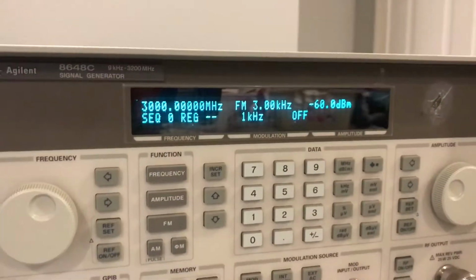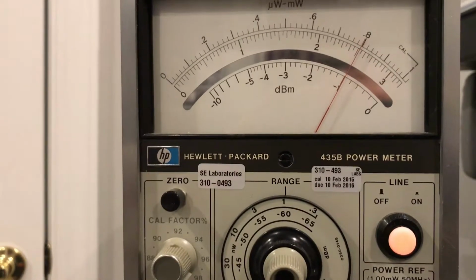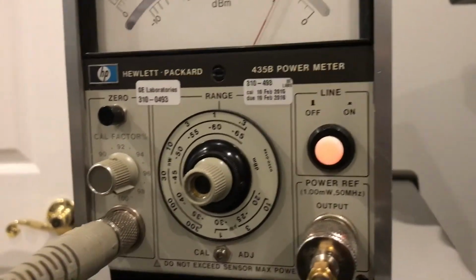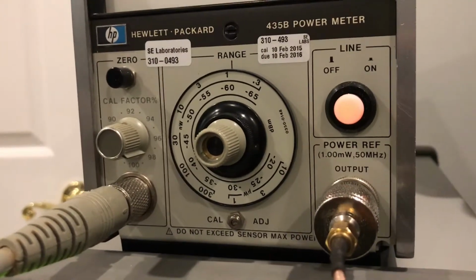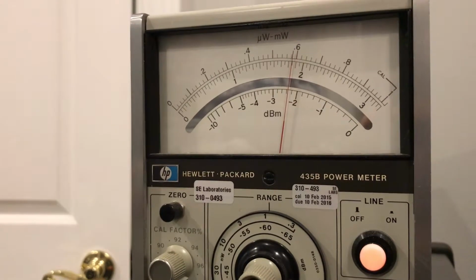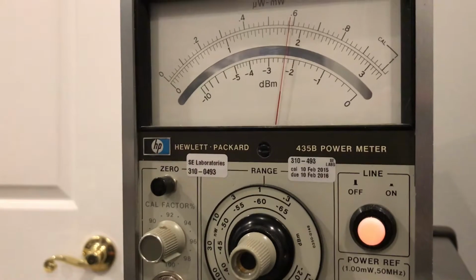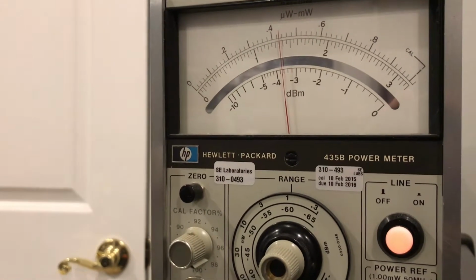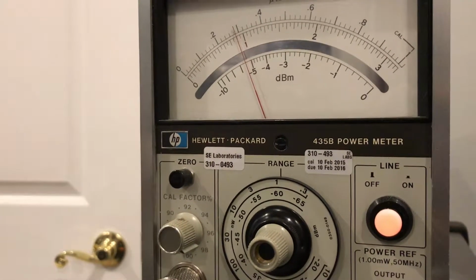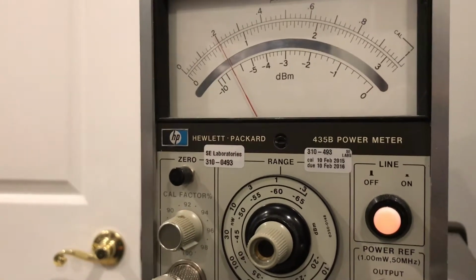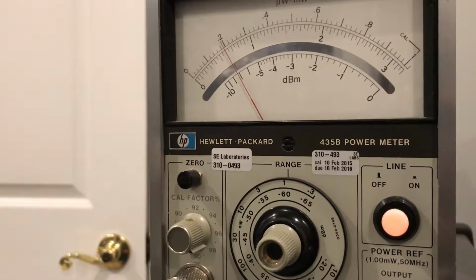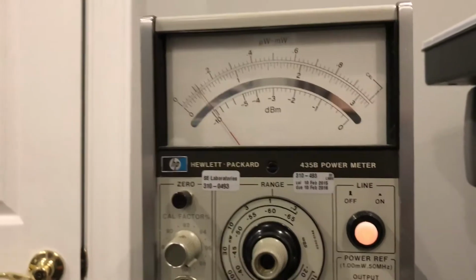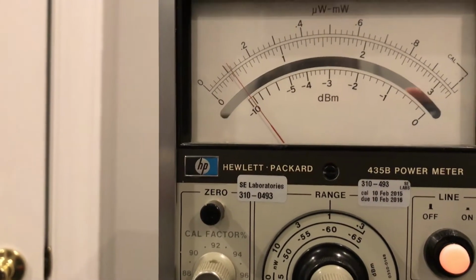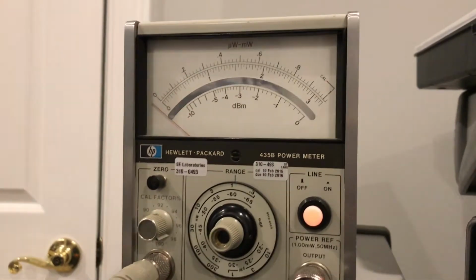Alright, so right now our attenuator is set for minus 60 dB, and we're actually showing a minus 61. So somewhere, and I'm just going to scroll the attenuator on the dial, and we'll see where we start getting this kind of response. So we're at minus 61, showing minus 62 on the meter. Alright, so now we're minus 62, minus 63, that's minus 64, so it looks like about minus 64 really starts to kind of come off the scale there as far as being on track, because that's again showing at minus 65 dB, and we're showing on the meter that we're already at minus 70. So this sensor appears to be not as well operating below.